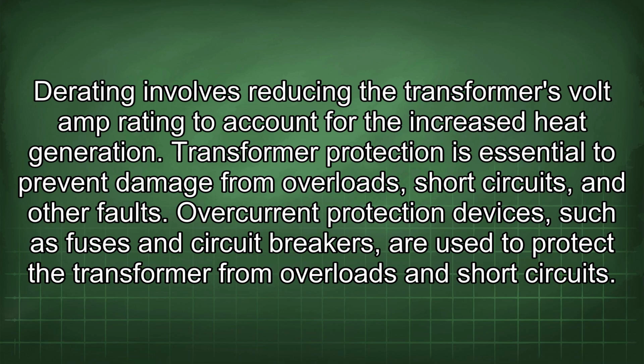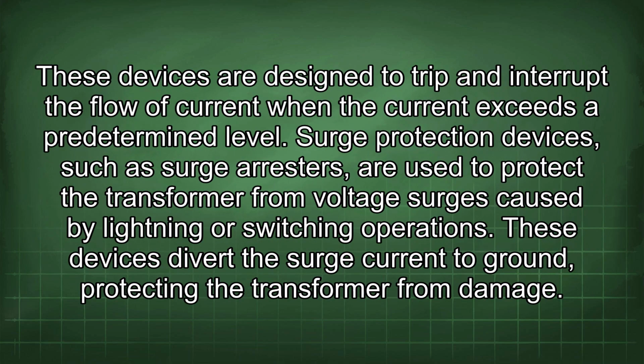Transformer protection is essential to prevent damage from overloads, short circuits, and other faults. Overcurrent protection devices, such as fuses and circuit breakers, are used to protect the transformer from overloads and short circuits. These devices are designed to trip and interrupt the flow of current when the current exceeds a predetermined level. Surge protection devices, such as surge arresters, are used to protect the transformer from voltage surges caused by lightning or switching operations. These devices divert the surge current to ground, protecting the transformer from damage.